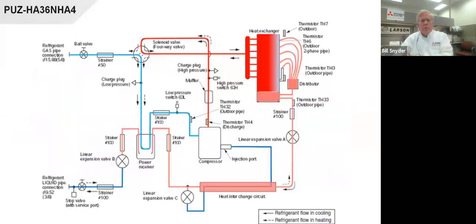Let me move on to this one. This is a PUZ. This is a P series, also a hyperheat. So it's got this circuit. If it's not a hyperheat, it will not have this heat exchanger circuit in here. But again, we have the thermistor measuring the discharge temperature of the compressor. You go through a muffler, through the reversing valve to the outdoor heat exchanger. So we're in the cool mode here, because we're dissipating the heat outside. Again, we have an outdoor ambient thermistor, and we have entering and leaving pipe temperature thermistors.